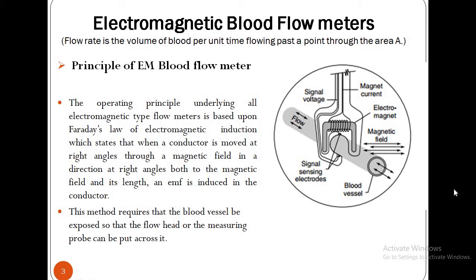The operating principle underlying all the electromagnetic type of flow meters is based upon Faraday's law of electromagnetic induction, which states that when a conductor is moved at right angles through a magnetic field in a direction at right angles both to the magnetic field and its length, an EMF is induced in the conductor. In the flow meter, an electromagnetic assembly provides the magnetic field placed at right angles to the blood vessel in which the flow is to be measured. The bloodstream, which is a conductor, cuts the magnetic field and voltage is induced in the bloodstream. This induced voltage is picked up by two electrodes incorporated in the magnetic assembly.